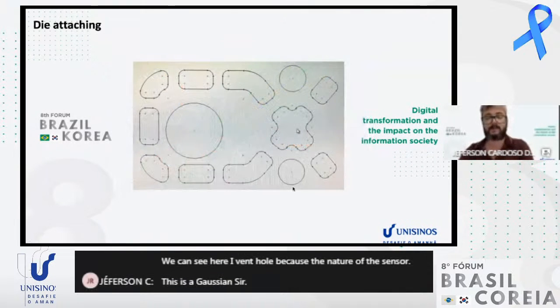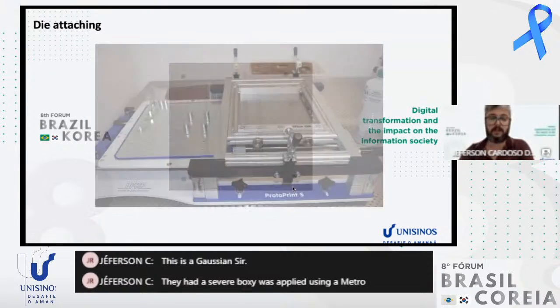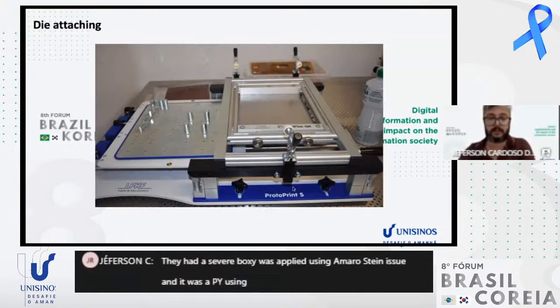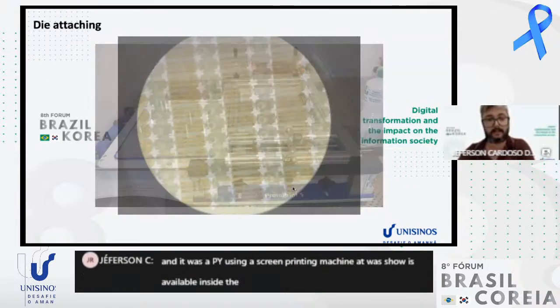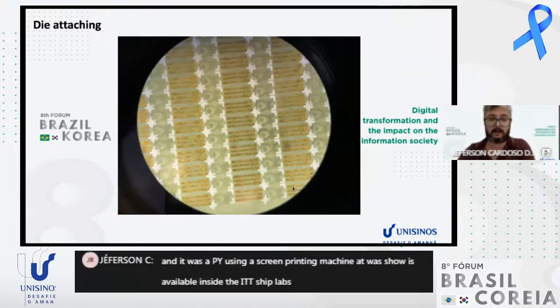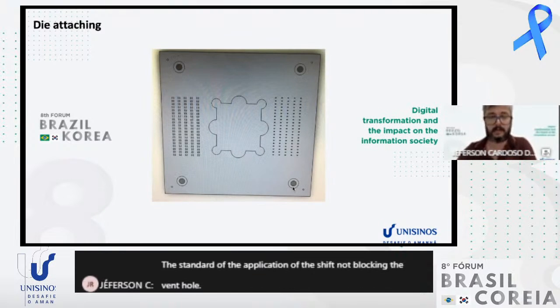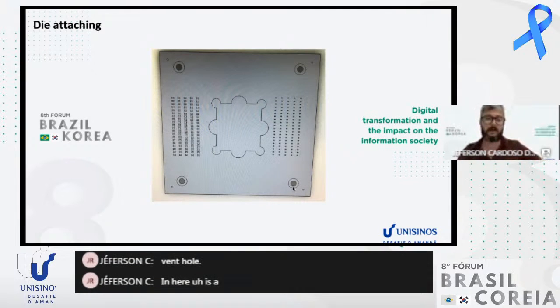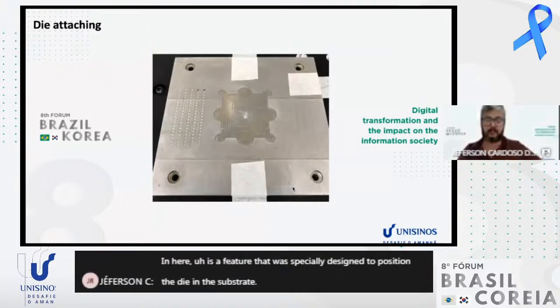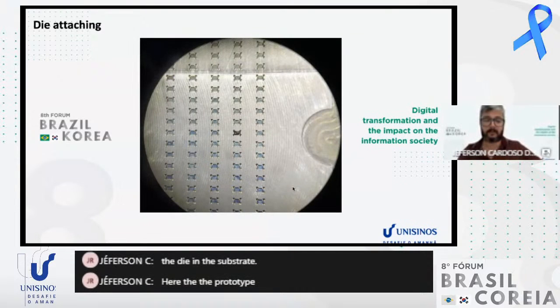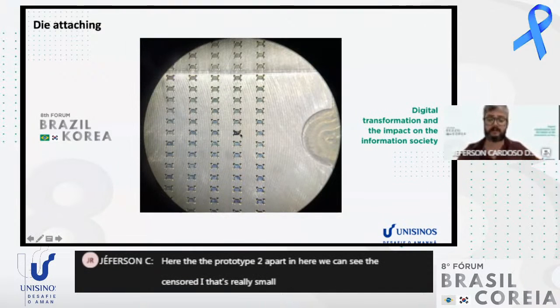The adhesive epoxy was applied using a metal stencil, applied with a screen printing machine available inside the ITT chip labs. Here we can see the standard path of the adhesive application, not blocking the vent hole. And here is a fixture specially designed to position the die in the substrate. Here the prototype part, and here we can see the sensor die, really small, inside the cavities.